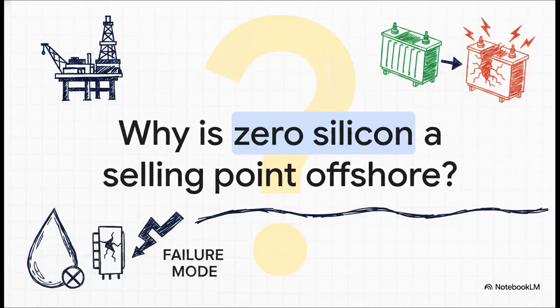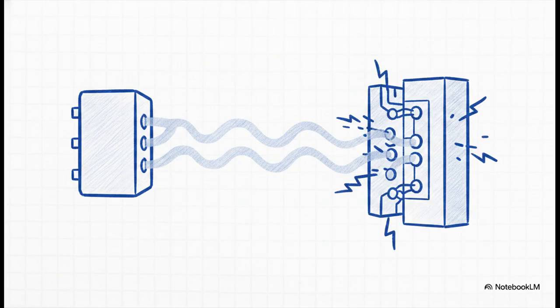So, quick check here. Why is zero silicon called out as a specific selling point for offshore use rather than just being some clever marketing language? Take a second to really think about it. If you're out there commissioning a rig, why on earth do you care if there's silicon in the construction of your transformer? Well, this isn't a buzzword. It actually points directly to a silent, real-world failure mode that has plagued operators for years. The culprit is silicon migration. It's a highly documented offshore contact fouling risk.